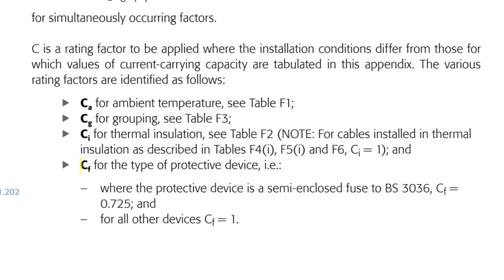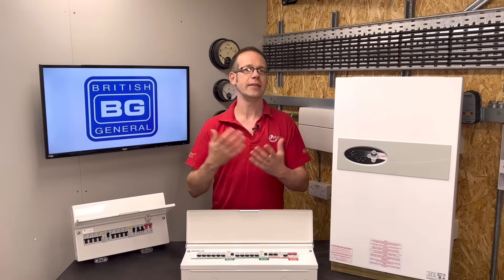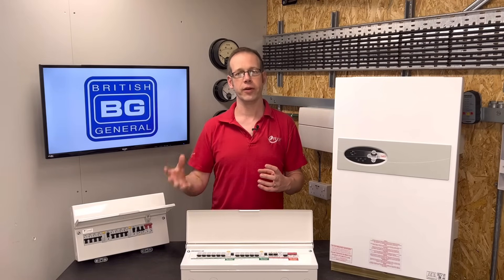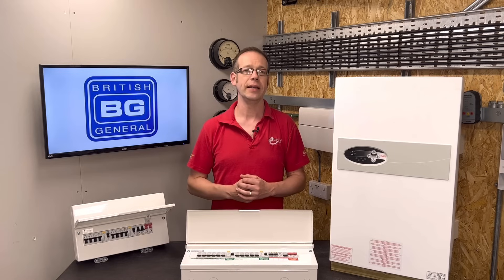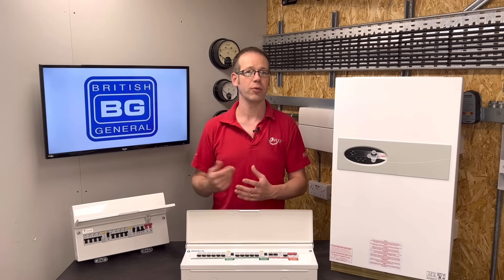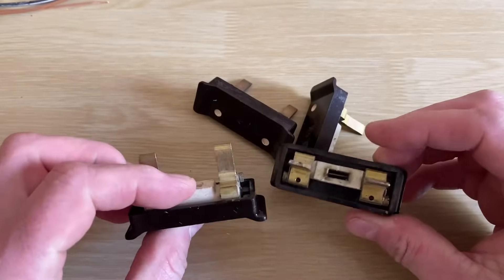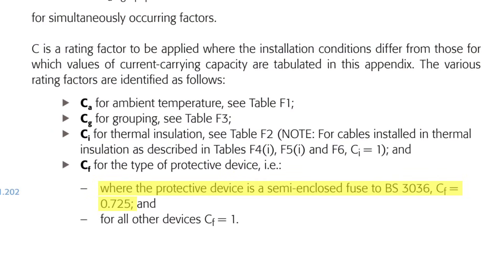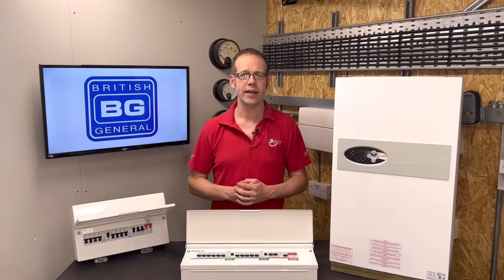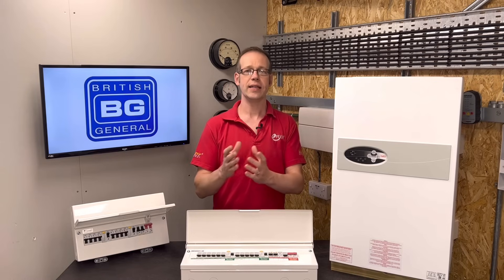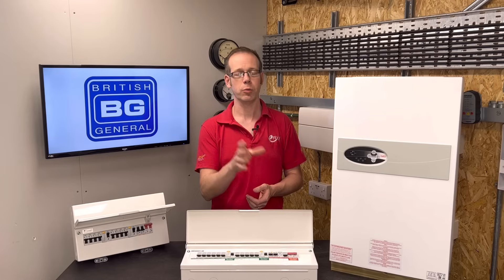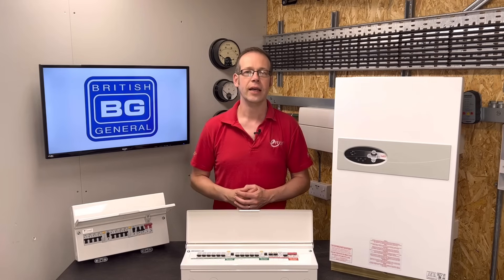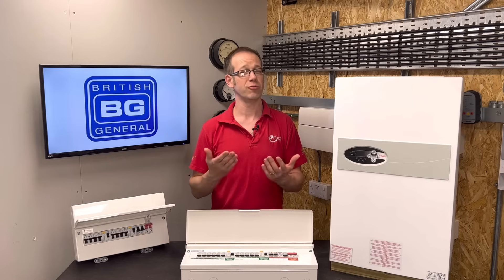Finally, CF relates to occasions when you may use a fuse to protect the circuit. A fuse is generally slower to operate when a fault occurs, meaning high current may flow in the conductor for longer, so the cable may need to be larger to dissipate the increased heat without damage. If you're using a BS3036 fuse — such as the old rewireable fuse with a replaceable wire — you may need to apply a rating factor of 0.725. For our example, we're going to use the values for CA and CG as discussed, but not apply CF as we wouldn't install a new circuit off a BS3036 fuse, and we'll avoid thermal insulation because it's really not good for cables.